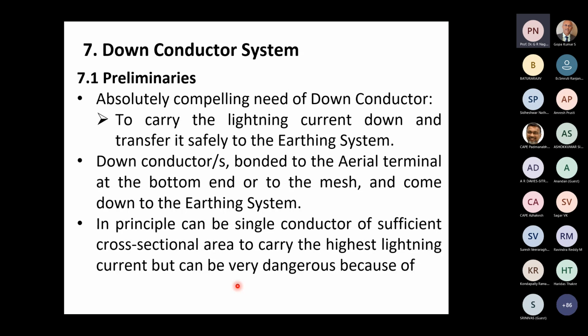This is the common understanding. But this common understanding is totally wrong, as we have discussed when we discussed the tall pole. The inductance and the surge impedance of these conductors become the prominent factors, and that produces high contact potentials and high ground potentials, which can be very dangerous. Even 50 kiloamperes in each of only 4 conductors, for the worst case, is still very, very dangerous, both for contact and for proximity. Proximity is even more dangerous because people can think, I'm not touching the conductor, therefore I'm safe. That is again a wrong notion. It's an illusion.